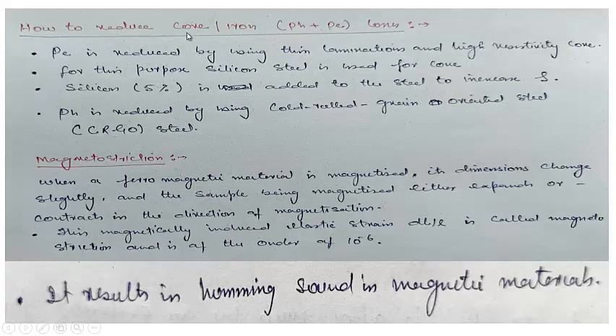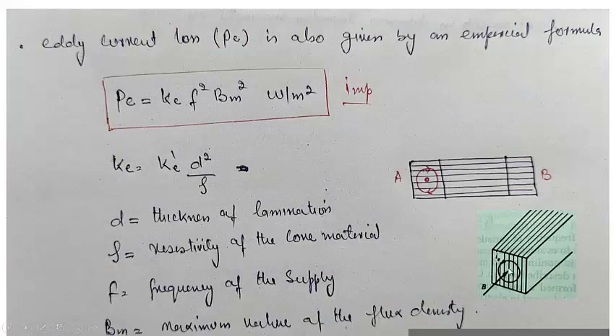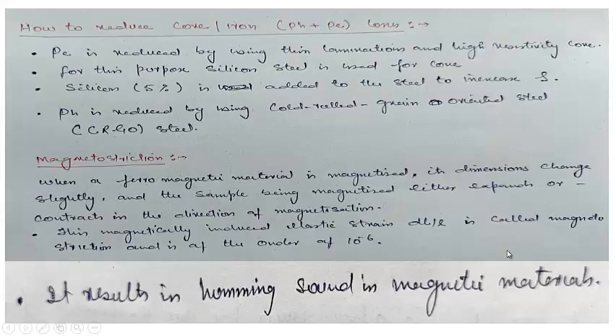Now, how to reduce core or iron losses. The combination of eddy current loss and hysteresis loss is sometimes known as core loss and sometimes as iron loss. Eddy current losses are reduced by using laminations and a high resistivity core. I have told you just now that thinner laminations can reduce the eddy current losses. The resistivity of the core is increased by using silicon steel, and 5% of silicon is added to the steel to increase its resistance. Beyond this, it makes the steel very brittle. So 5% is the optimum value, as it serves the purpose of increased resistivity and lesser brittleness of the core.